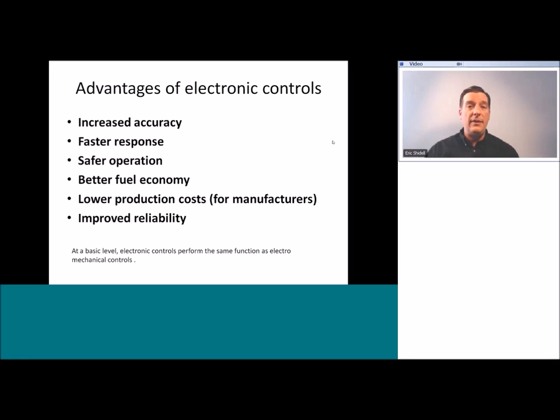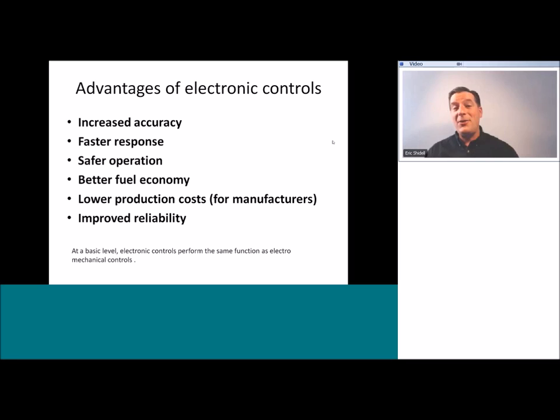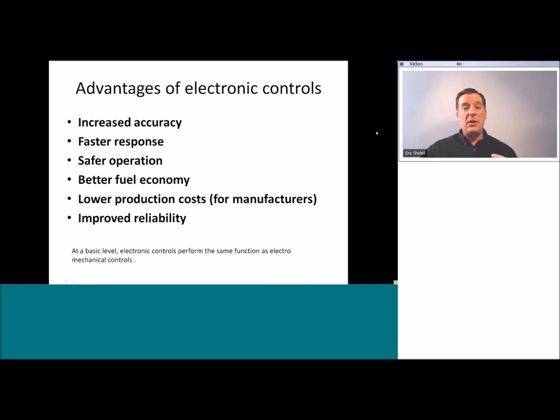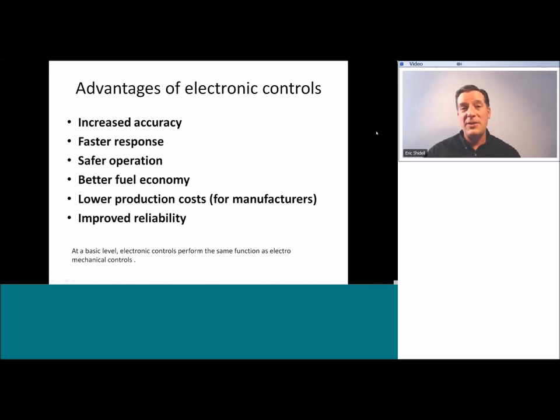The power switching contacts for the compressor and condenser fan also have a much higher duty cycle than traditional contactors, so this contactor will last three to five times longer. I want to show you that to illustrate the advantages of electronic controls replacing electromechanical ones. Once I explain all the things this device does, those of you with air conditioning experience would say you can think of a lot of applications where this would be tremendous value. And these are the reasons why we need electronic controls rather than simpler older methods.